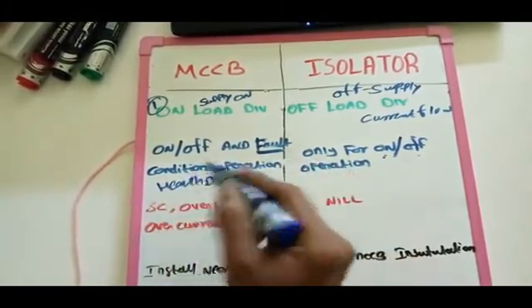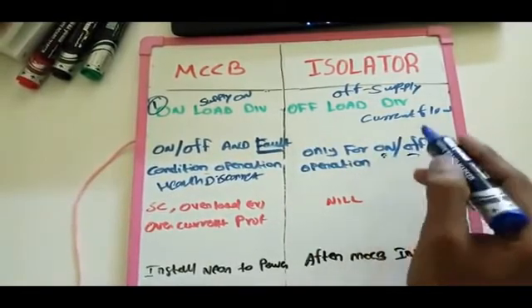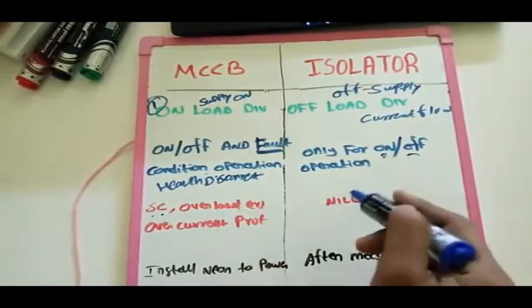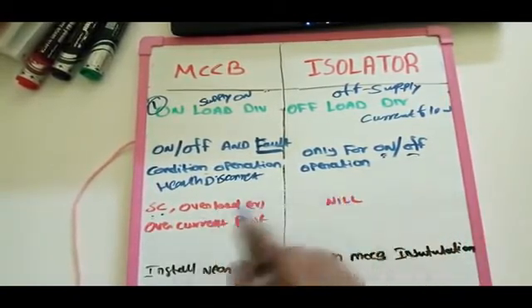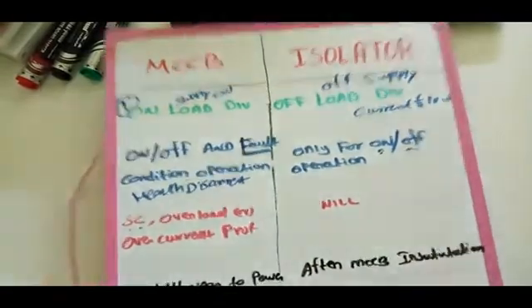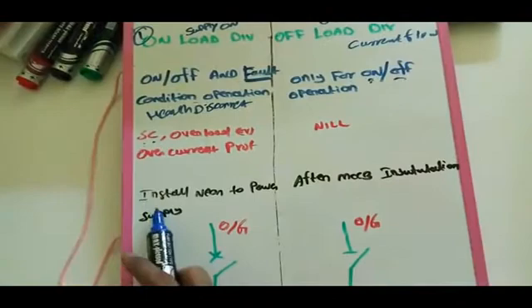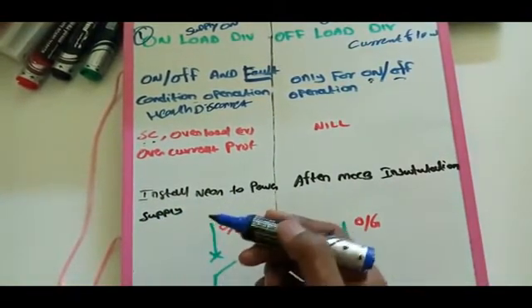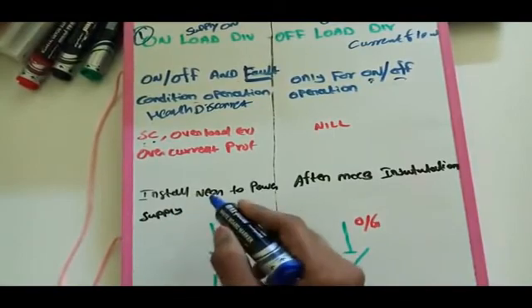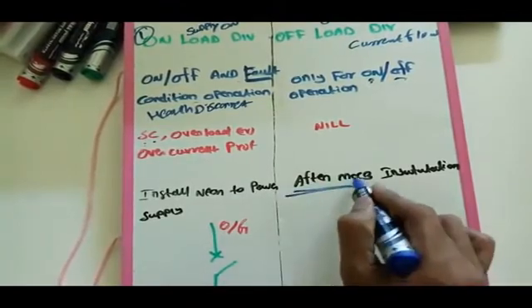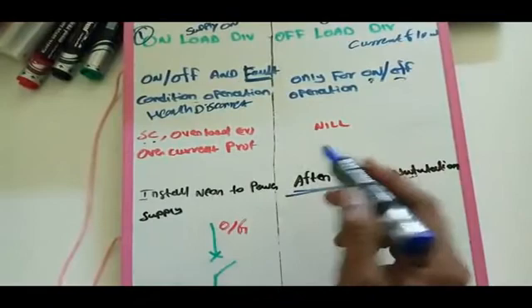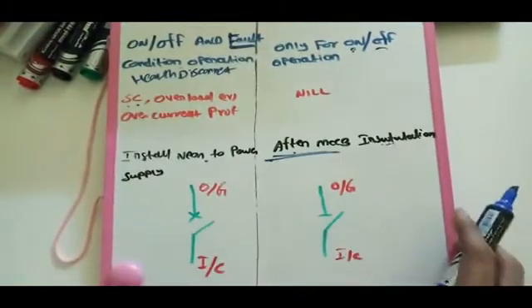The Isolator only has switch on and switch off operations. Short circuit current protection, overload, and overcurrent protections are available in MCCBs but not in the Isolator, because the Isolator acts only as a switch. The MCCB should be installed first because it provides protection to the circuit. The Isolator is installed after the MCCB, as the MCCB is the primary switching and protection device.